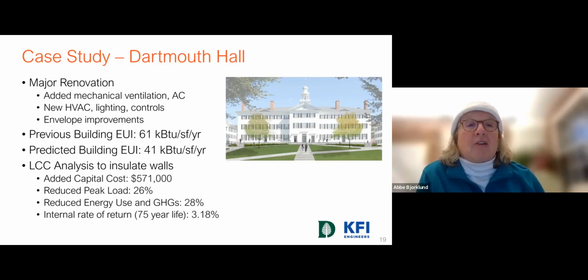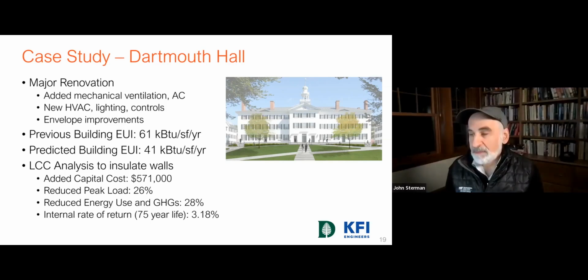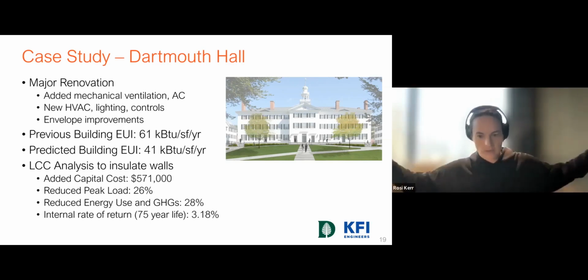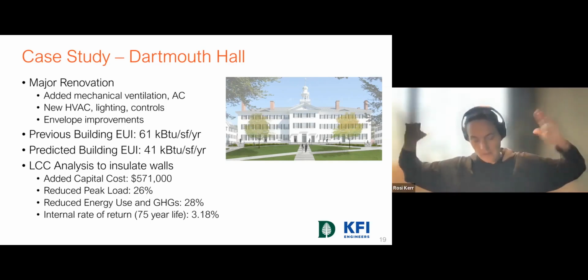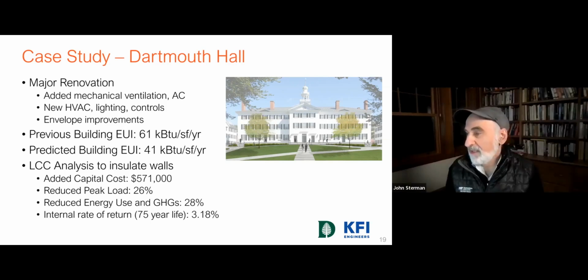When we went through that process, looking over the life cycle of the insulation, we thought it was reasonable to set it at 75 years. So even though it was more than a 60-year simple payback, the administration agreed we should go ahead and insulate these walls, and it still has a positive internal rate of return of over 3% over the 75 years. I think this building represents a huge victory, even though it's not the biggest building or the biggest energy user, but it's the most iconic, famous building.